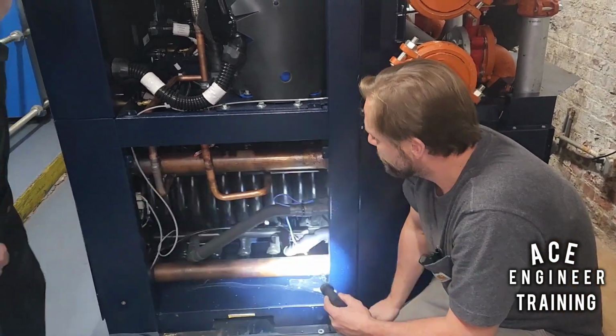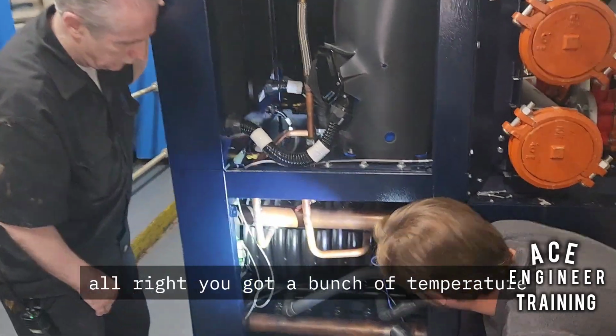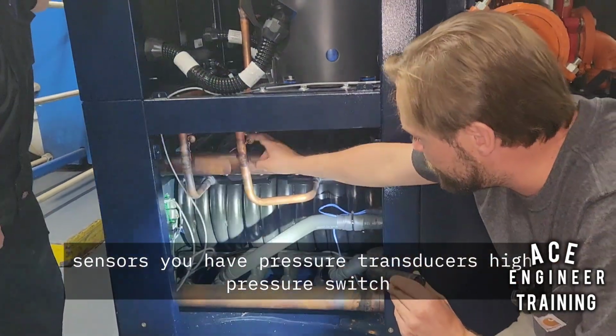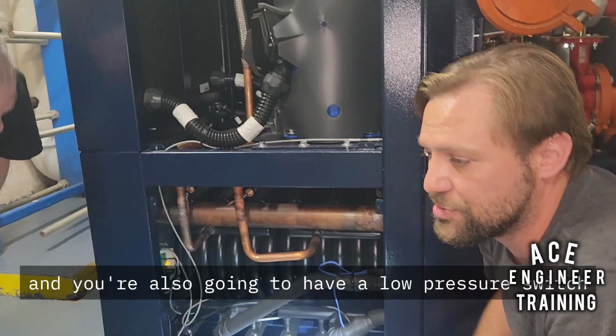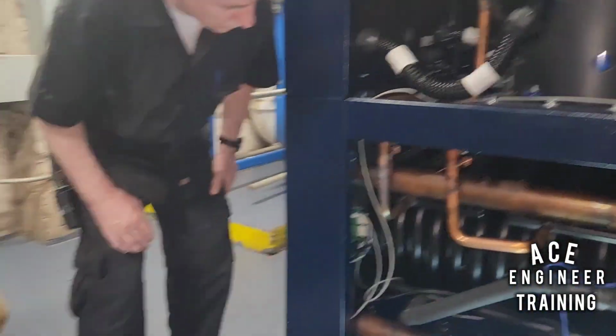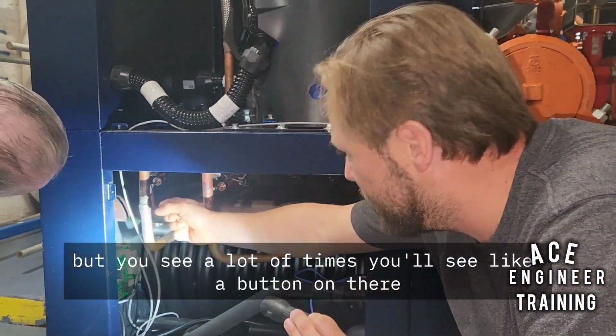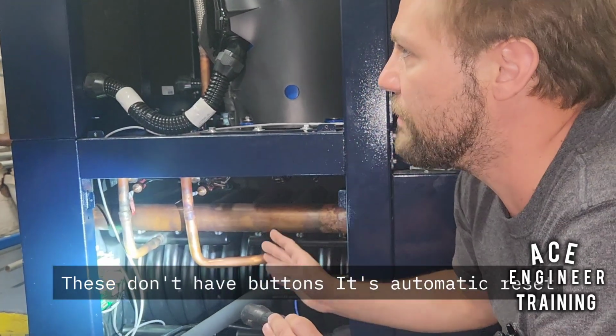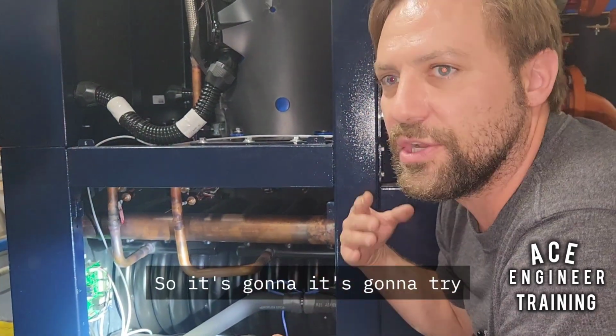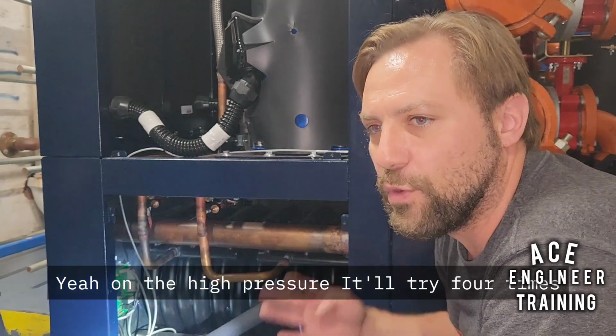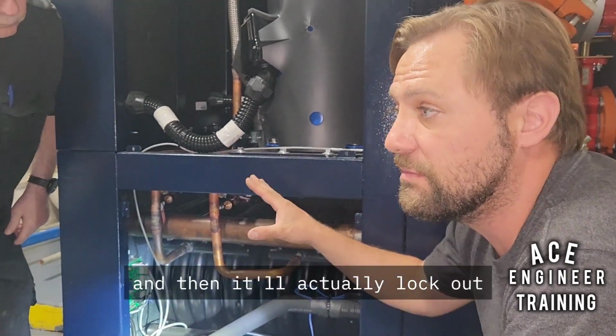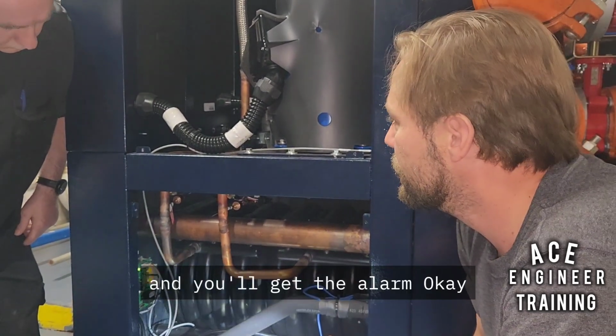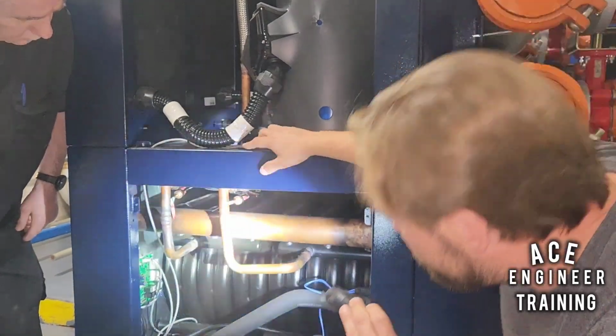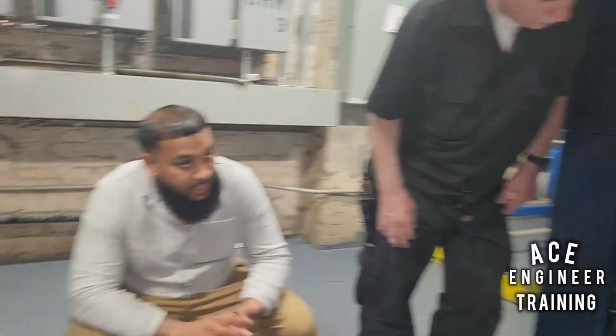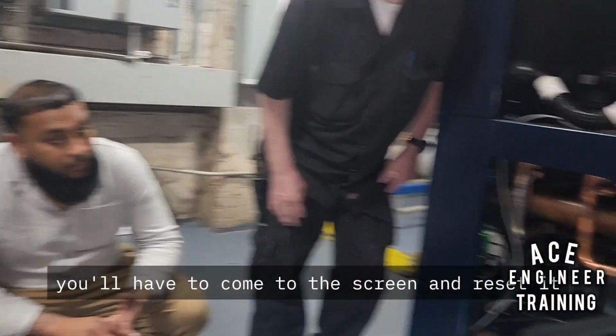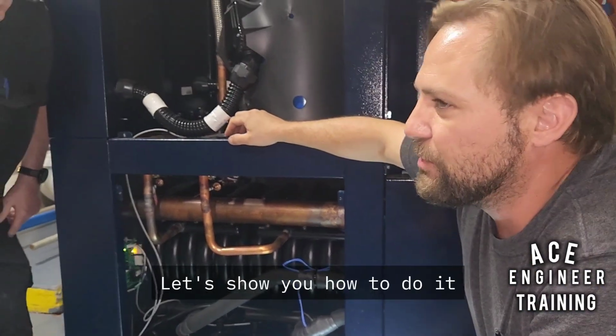Okay. All right. And you got a bunch of temperature sensors. You have pressure transducers, a high pressure switch, and you're also going to have a low pressure switch, which are automatic reset. So this is a high one, but a lot of times you'll see a button on there. These don't have buttons. It's automatic reset. So on the high pressure, it'll try 4 times, and then it'll actually lock out, and you'll get the alarm. Okay. All right. So it automatically resets by itself. So once it locks out, you'll have to come to the screen and reset it. Reset it from the screen. Which we'll show you how to do.